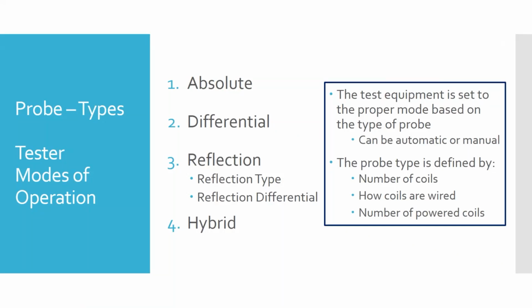And so you have the modes. On our testers you can select between absolute, differential, or reflection probes, and if you have a hybrid you have to know which mode it's supposed to operate in, which one it should look at. The probe type can be defined by number of coils and how they're wired, in series or in parallel, or a combination of the two. You might have a couple of coils in series and then another one in parallel.